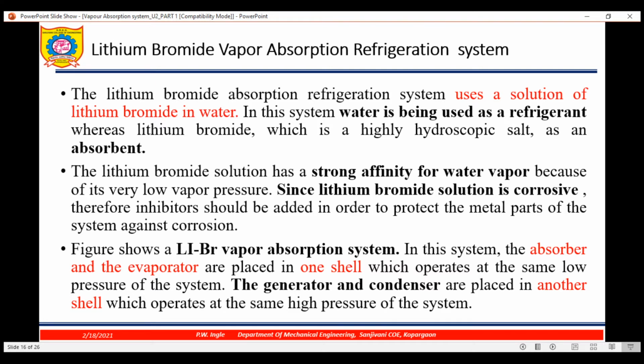Okay, so I'll read some important points. The lithium bromide absorption refrigeration system uses a solution of lithium bromide in water. In this system, water is used as a refrigerant, whereas lithium bromide, which is a highly hygroscopic salt, is used as an absorbent. In short, in this lithium bromide vapor absorption refrigeration system, we are using water as a refrigerant and lithium bromide as an absorbent.